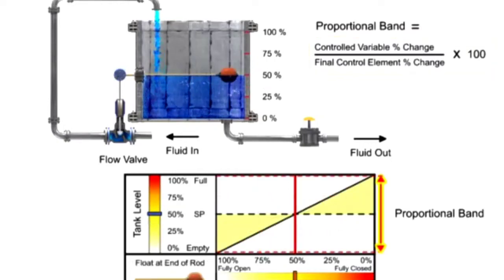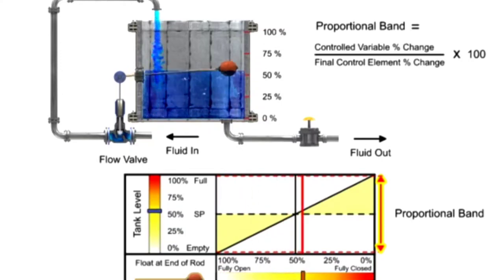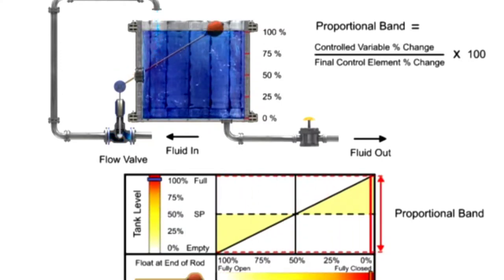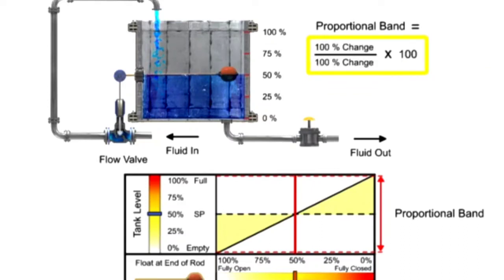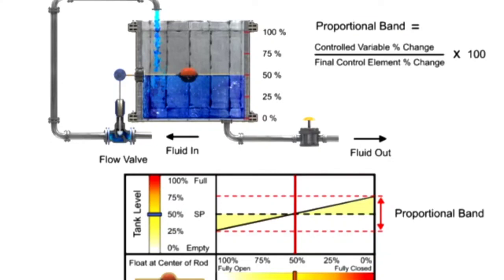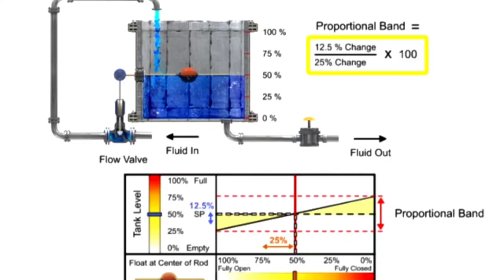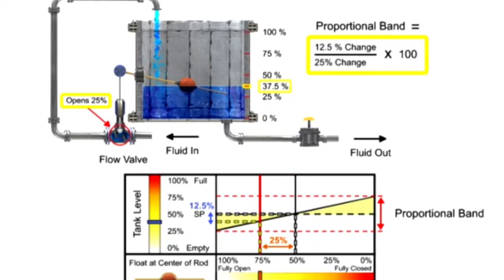The width of the proportional band determines how much of a controlled variable change is required to cause the final control element to move by a determined amount. By placing the float on the end of the rod, the fluid level has to change 100% to cause the final control element to change 100%. By placing the float at the center of the rod, the fluid level has to change 12.5% to cause the final control element to change 25%, reducing the width of the proportional band by half.